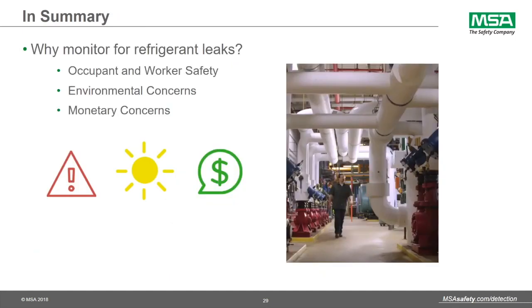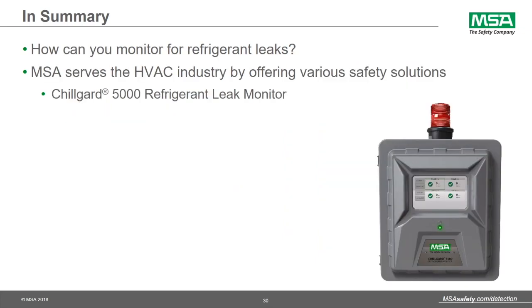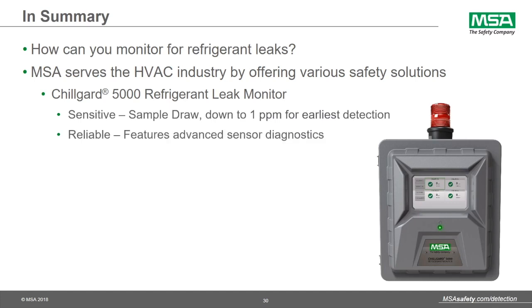So in closing, we monitor for refrigerant leaks for worker safety, environmental concerns, and economic reasons. The Chillgard 5000 refrigerant monitor is a safety solution to mitigate harmful and costly refrigerant leaks. It's sensitive, getting down to 1 part per million, providing you with the earliest level of leak detection. It's reliable, where it has advanced diagnostics, and it keeps you compliant with ASHRAE 15.